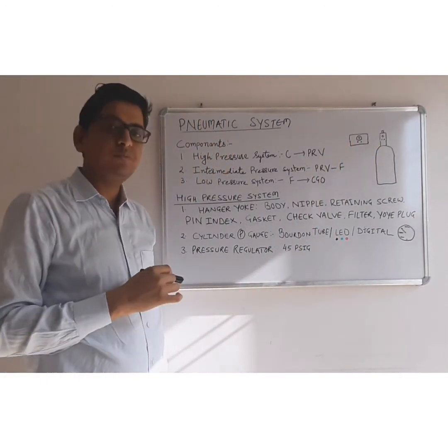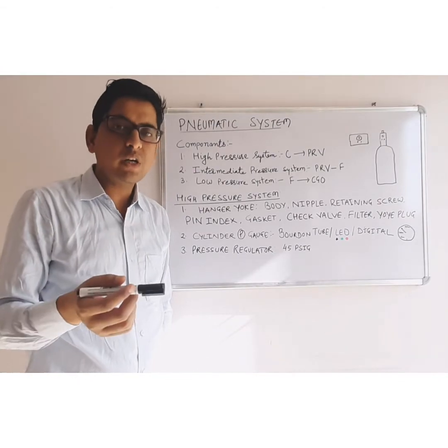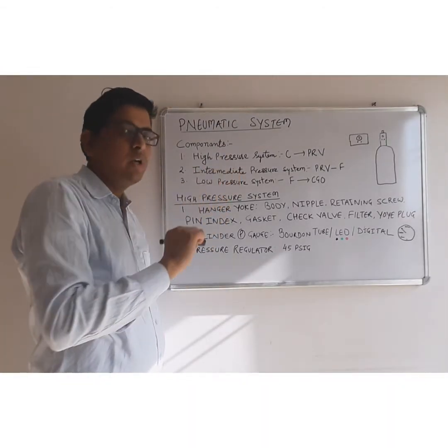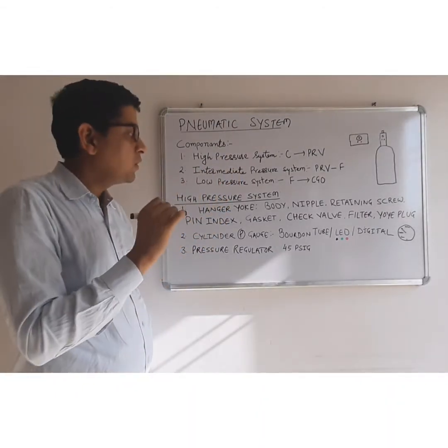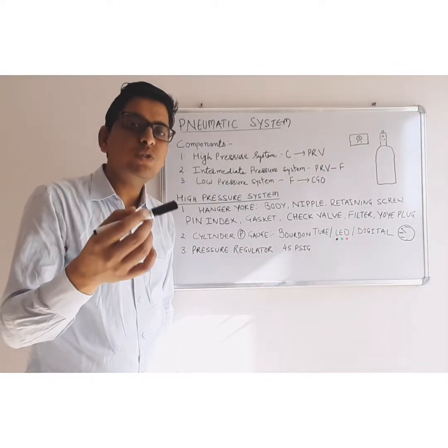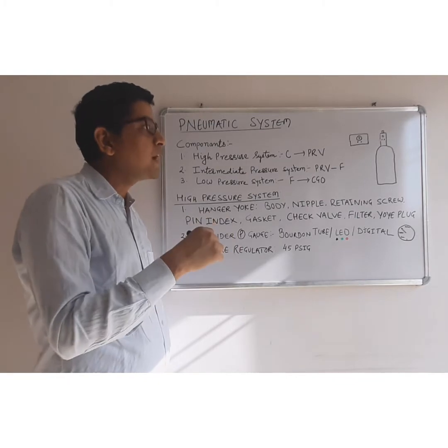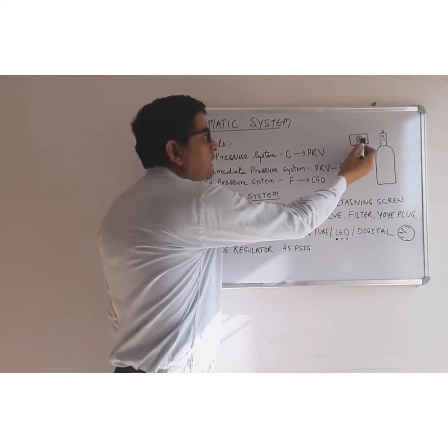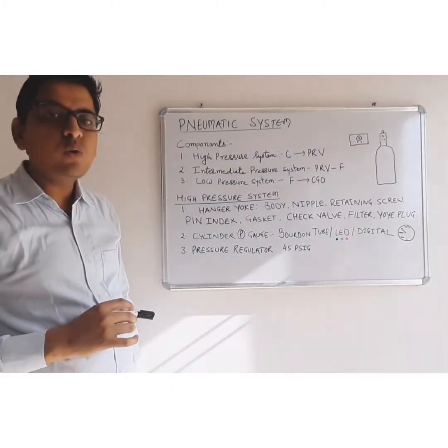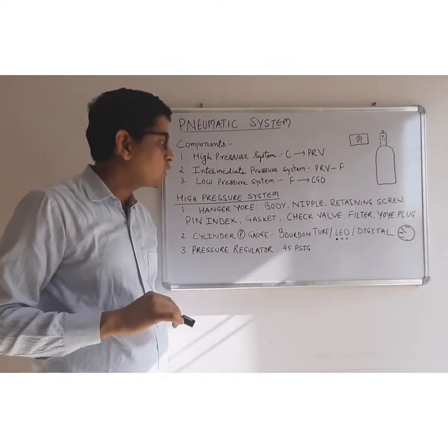In case there is no washer, it can lead to leakage of the gas around the nipple, while if we are using more than one washer at a time, it can bypass this pin index system and can lead to attachment of the wrong cylinder.